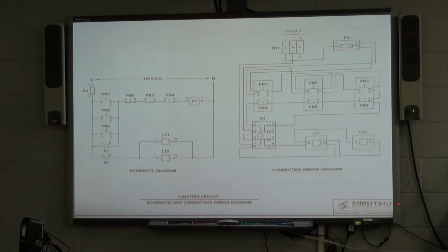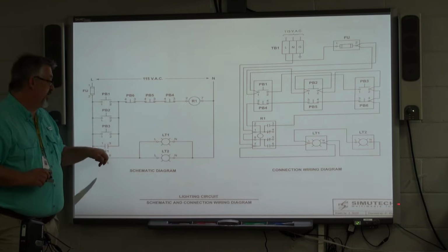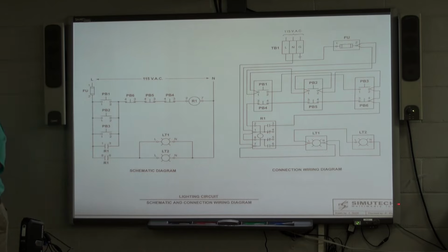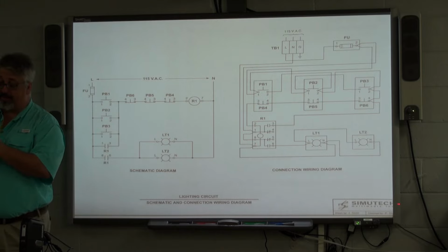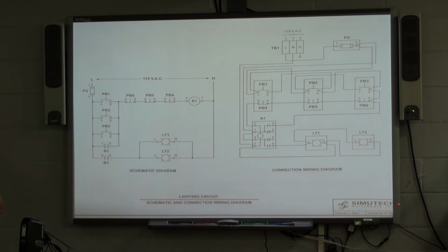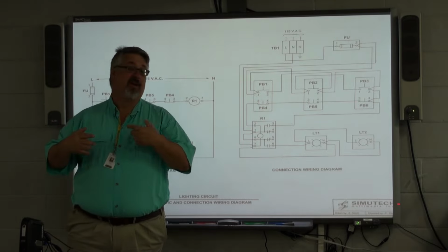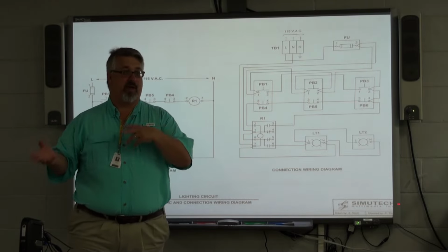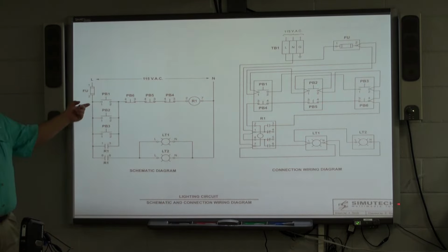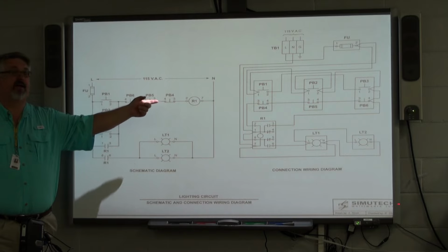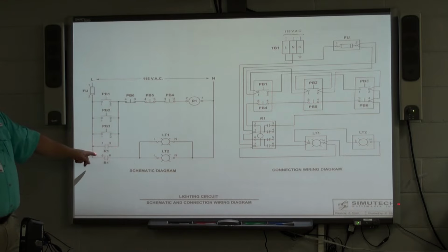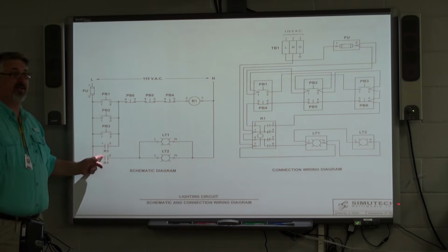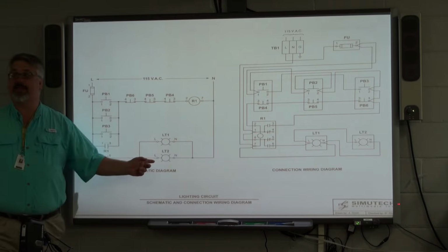I've got a set of contacts over here that when that relay is energized, closes, and I've got another set over here that when that relay energizes, closes. I can hook whatever I want to those. They're mine to use. If you look at the front of it that has the writing on it, you'll see a couple of copper contacts, and both of those engage when we apply voltage to the coil. The normally closed go open, the normally open become closed. So as soon as we press a button, we send a voltage to that relay. Once we press that button, 120 volts is provided through the contact that's tied to pin 8 over to pin 6, turning on this light.